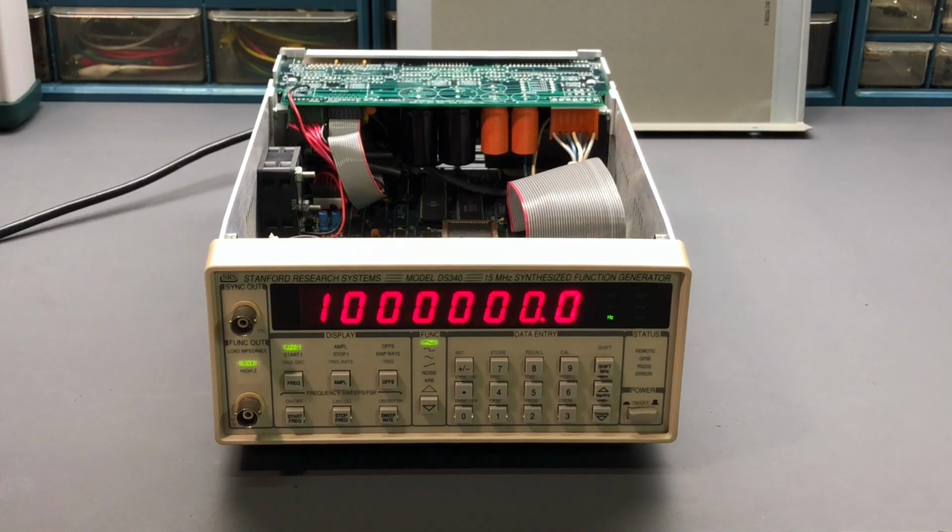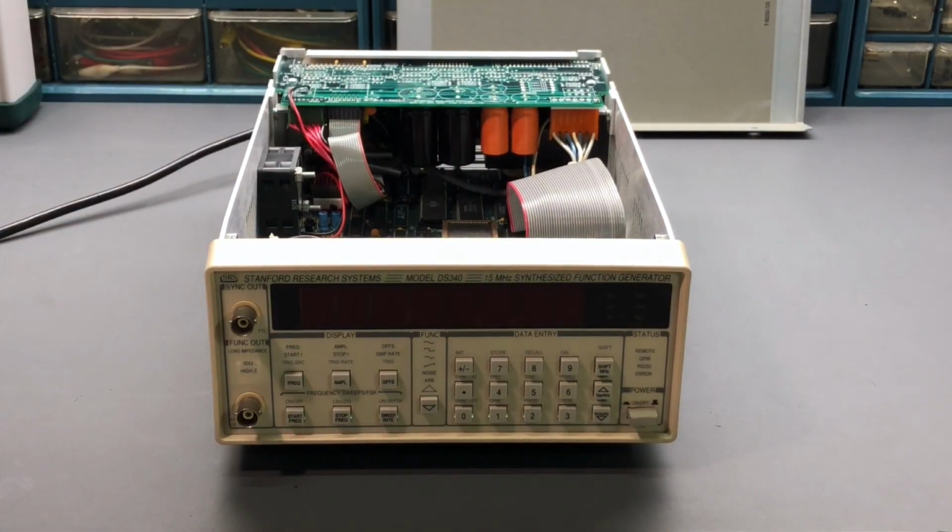So let's power down the instrument. Okay. Now the memory retention battery should be holding up the RAM. That data should remain. Okay, so we'll just give it a little bit here. And it should now start up correctly because all of the calibration constants are being retained in RAM. Okay, a copy has been moved over. And then we'll proceed, if that is true and there's no further issue, with changing the cal byte that's related to the frequency, because that seems to be where most of the calibration error is occurring as far as the deviation from where it should be.